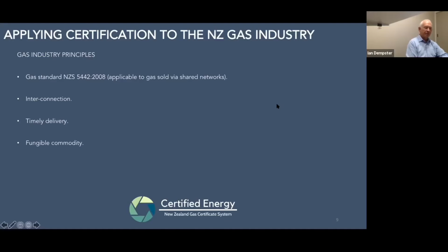So, if you get to something that is mostly methane, I think you probably are going to meet the gas spec. But biogas in the raw sense, by the time you look at the water content and the CO2 content and so on, it could be a country mile away from spec. So you wouldn't want to be doing that.